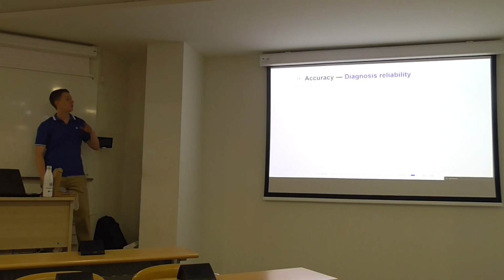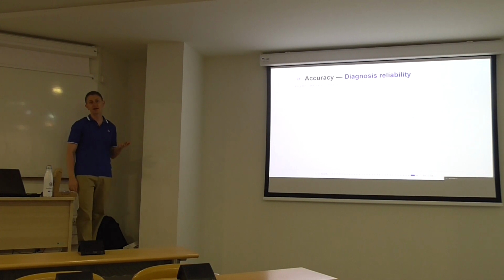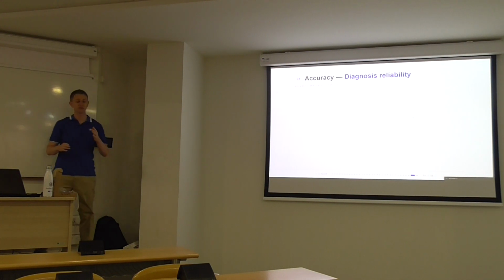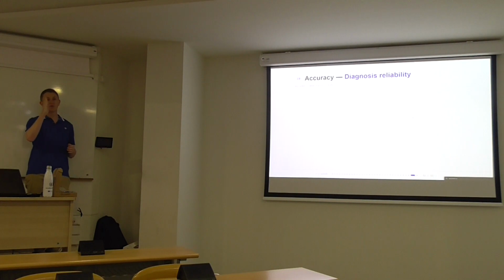And finally, we have also studied the diagnosis reliability. What we have done here is easy. The broken bar harmonic is not a thin line. It's something like that. So we have gone spectrum through spectrum, recording the maximum amplitude of that harmonic, just in the peak. Then we take the rotor slot harmonic, estimate the speed, with that speed we compute the frequency, and we see what the amplitude is at that exact frequency. Maybe the real amplitude is here, and with my frequency, I'm here.